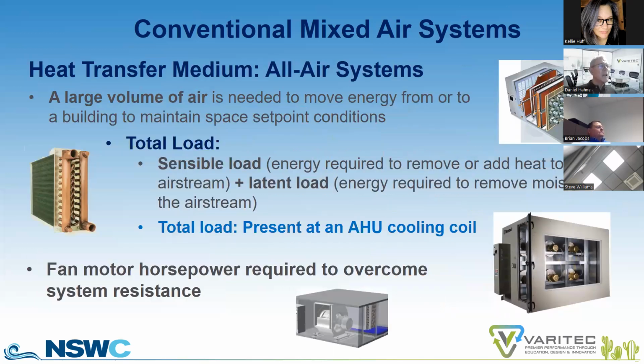So consequently, in an all-air system, if you're using air as your heat transfer medium, because of air's less dense properties, you need a large volume of air to move the energy in a building to outdoors in order to maintain space set point conditions. And you see that total load, which is comprised of the sensible load and the latent load as discussed previously, at an air handler cooling coil. All of the load is seen at the cooling coil. That's where you see your sensible cooling as well as your latent cooling. Consequently, you need a lot of fan horsepower to move the amount of air necessary to condition and satisfy a building.